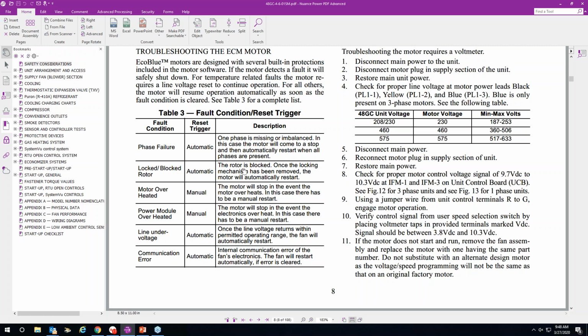But that's the other thing that's causing limit lockouts that we've been chasing, because we've had reports back from you guys that the motor just isn't running. Sometimes the motor is hot, and you let it cool off, turn the power off, and sure enough, you turn it back on, and 9 out of 10 times it starts. Sometimes the guys will say, I just gave it a spin, now it's running. That's all getting this locked or blocked rotor fault code to release. And typically it was because of high voltage or possibly this high leg delta power supply.